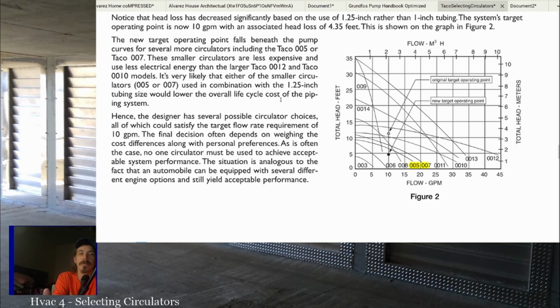But in 5-10 years, when they have to replace that pump, it's going to cost them $300 every time they have to replace the pump, as opposed to the 007, which will cost them $100 every time. So you're lowering their overall life cycle cost of a system. And generally, on a boiler system, you should figure that system's probably going to last 40 or 50 years at least. Boiler systems go for a pretty long time if everything's held in pretty good shape. So you want to figure about a 40 or 50-year life cycle cost at least for a system like that, if not 100 years. A lot of systems are designed in buildings to last 100 years if possible.